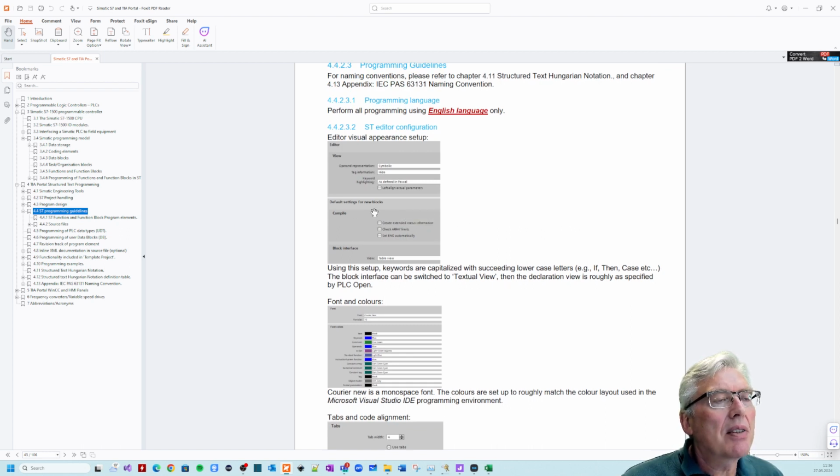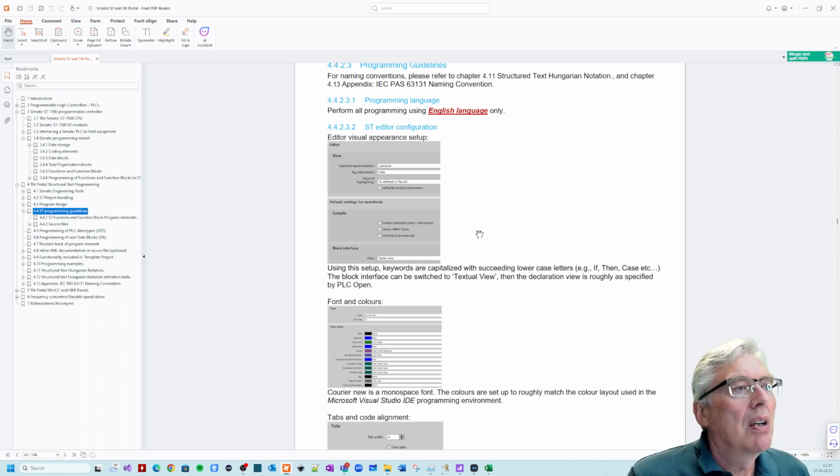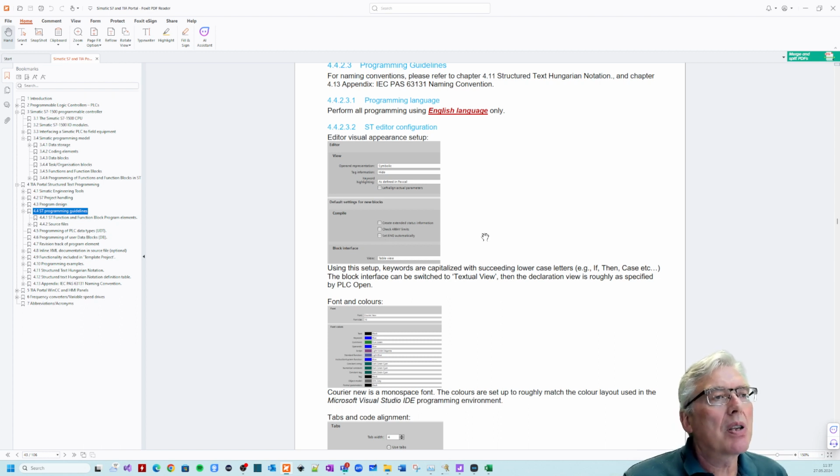This extended status information is for debugging and so on. Error limits, you can check those. Don't do it, because if you are messing around outside the error you have declared, there's an error in your program, and your CPU might as well stop, because you don't know what's going to happen next. And enable output is for ladder and FBD programming. Of course, we are not programming ladder and FBD.